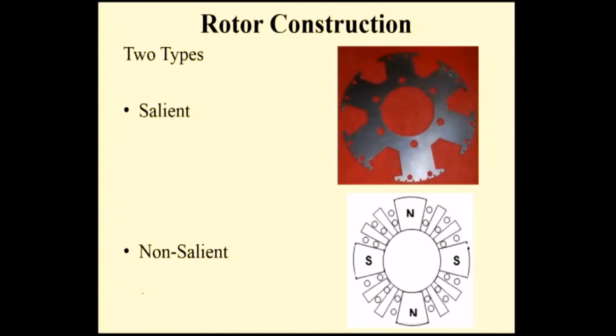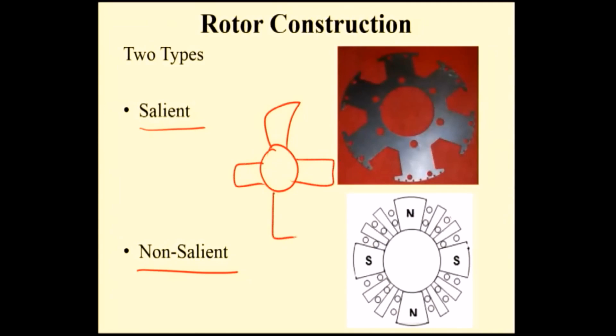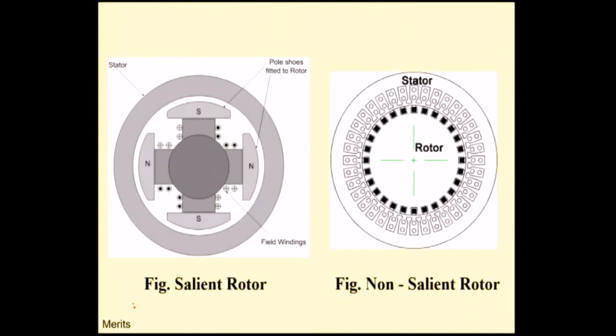Now for rotor construction: the stator inner periphery has slots, and the stator stamping is made of silicon steel or good magnetic material to reduce eddy current loss and hysteresis loss. There are two types of rotor: salient pole rotor and non-salient pole rotor. Salient pole rotor has projected poles — the poles are projected outward. Non-salient pole rotor is a smooth cylindrical type. In a salient pole rotor the air gap is non-uniform, whereas in a non-salient pole rotor the air gap is uniform. This is the key difference between the two types.